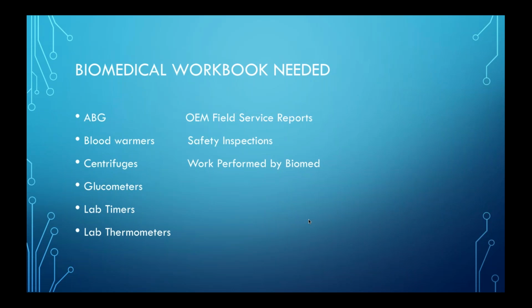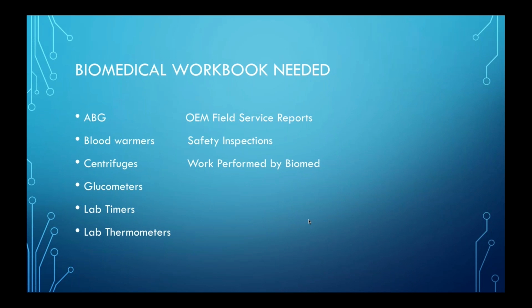The importance of this: usually when CLIA comes in to inspect, they want to make sure that the centrifuges had all the speed tested on them. They want to make sure it was proved. And they also want to see the test equipment that was used, because now DNV and the Joint Commission are starting to do this. They want to make sure the test equipment that we use to test the centrifuge on the spinning, and that's just an example, it's basically on all the equipment that's being used out there, correlates. So we document that on the work order.